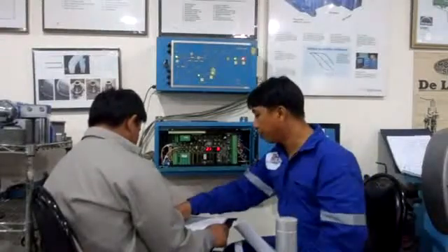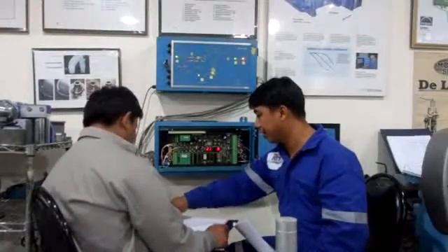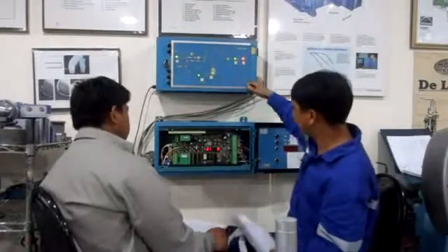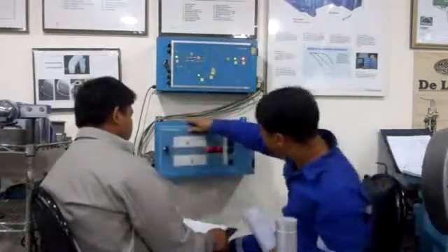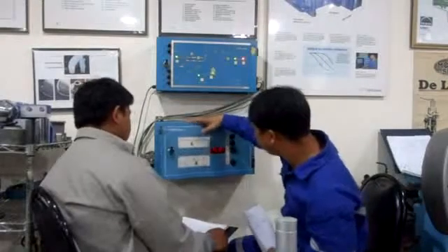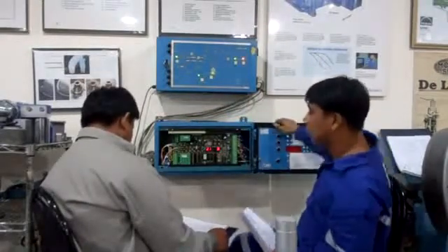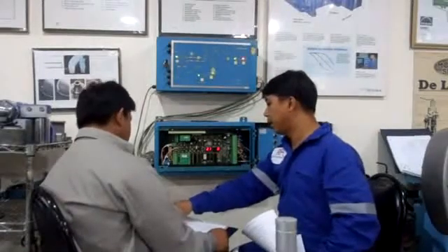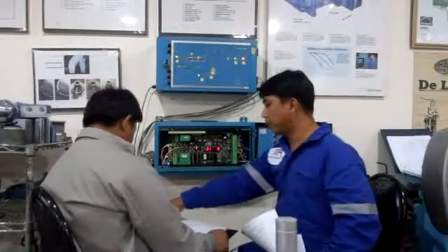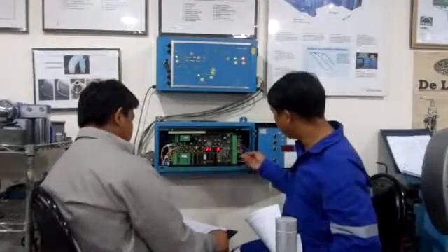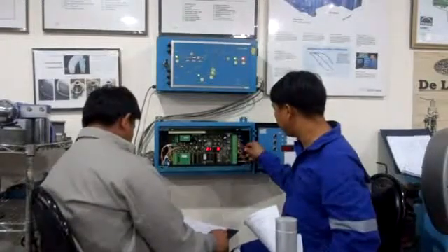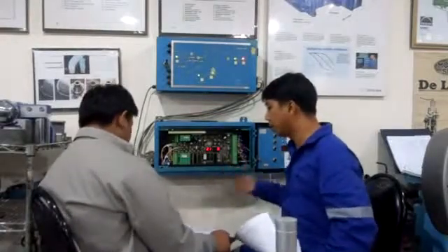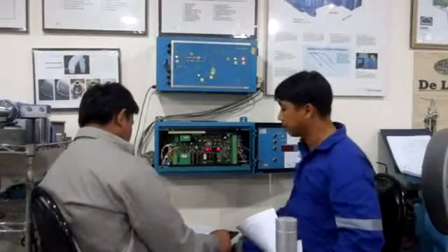Okay? And then we have the pressure switch indicated on the unit. That is supposed to be the pressure switch. So it's indicated here. Okay? PS42, if we have the alarm. At the same time, with this internal test program, we could see all of this wiring connection sometimes is lost. Okay, that's why we use this for the fault findings.